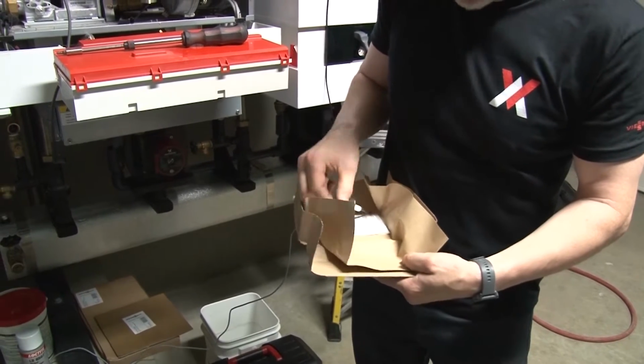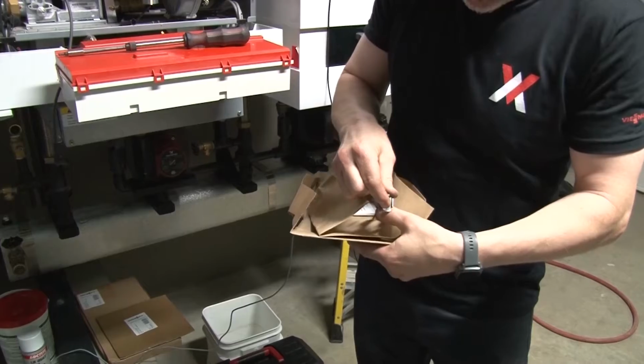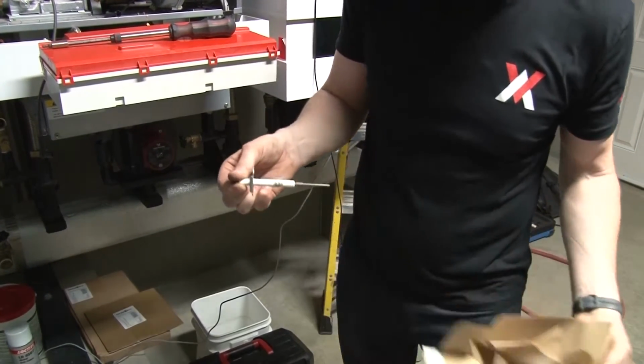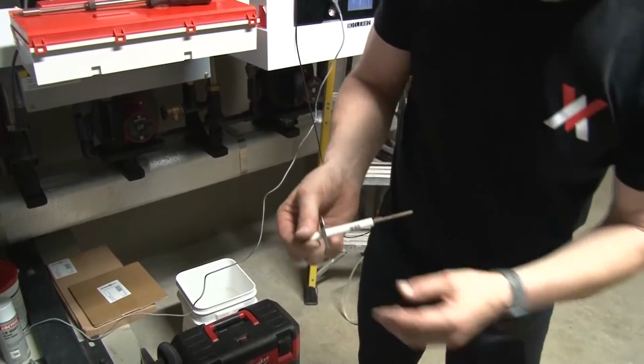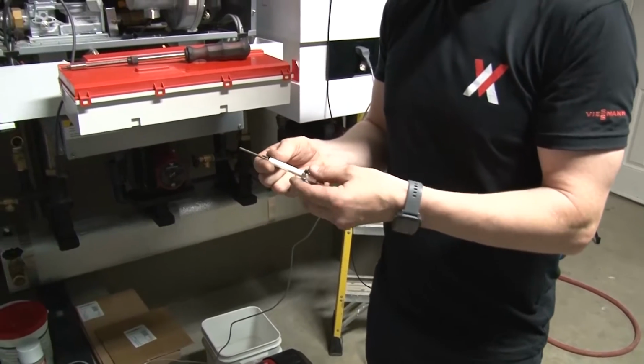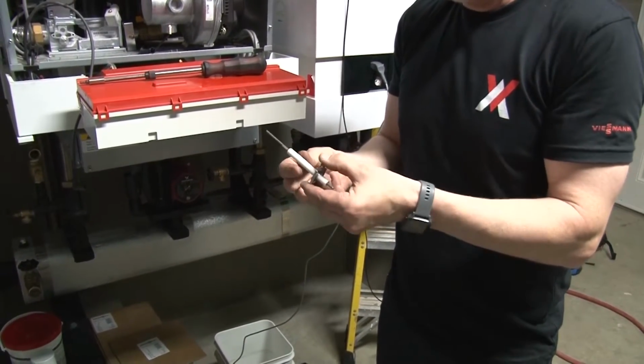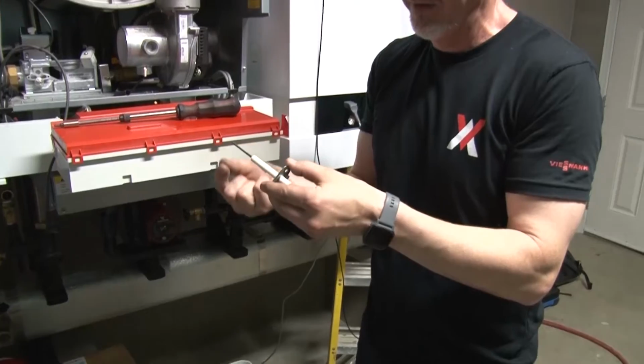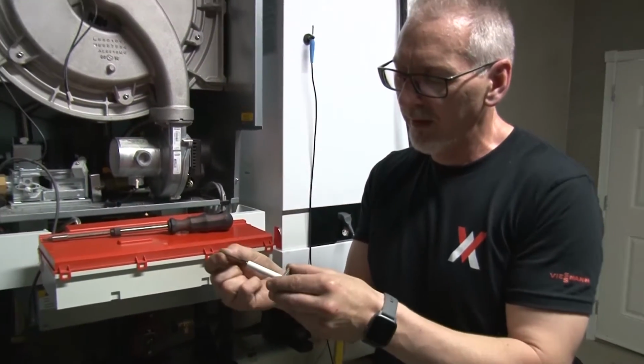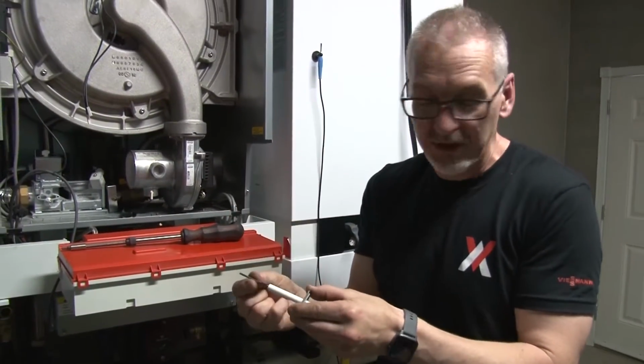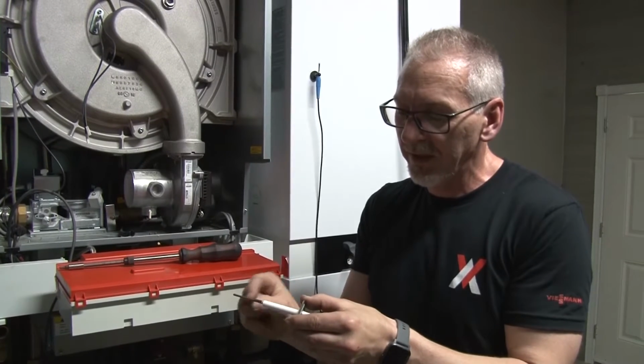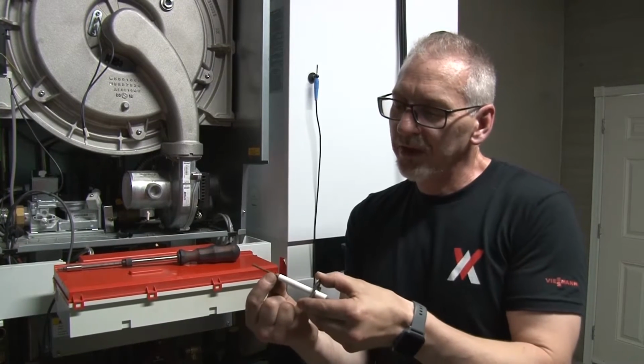Larger sizes, just from tech and troubleshooting and stuff like that, we found we get a little bit more longevity out of these particular electrodes as far as flame safety. And what they're called is a knife electrode or nickel ferrous. So this is the ferrous part of the electrode here. It's standard, it's the same as the one we just pulled out, but it has an extra little piece of nickel welded on here, a little closer to the burner mesh.